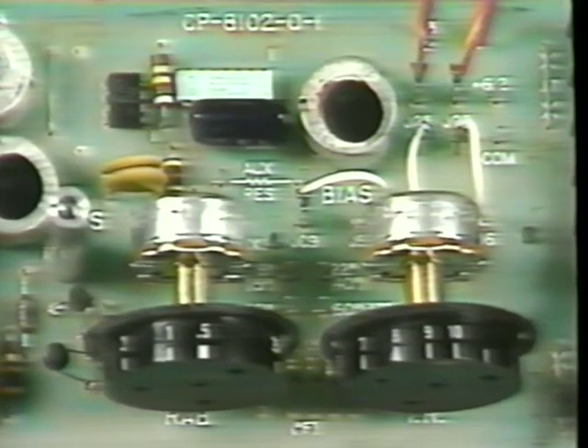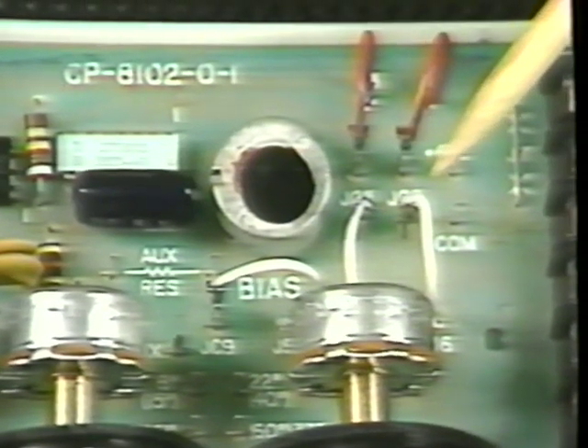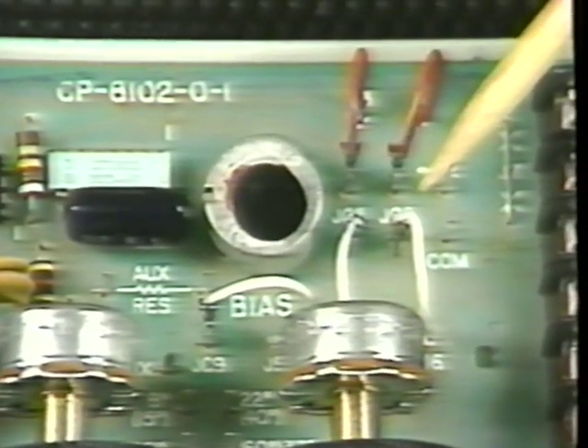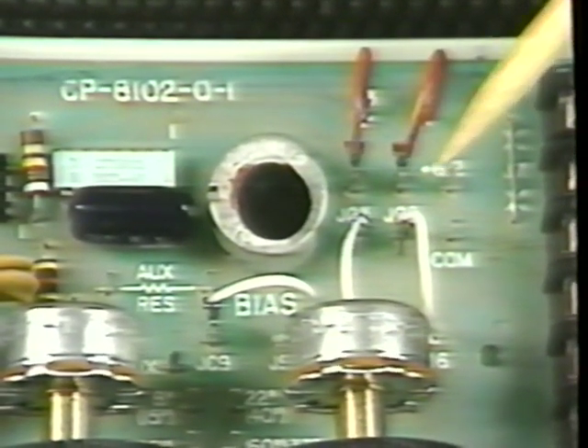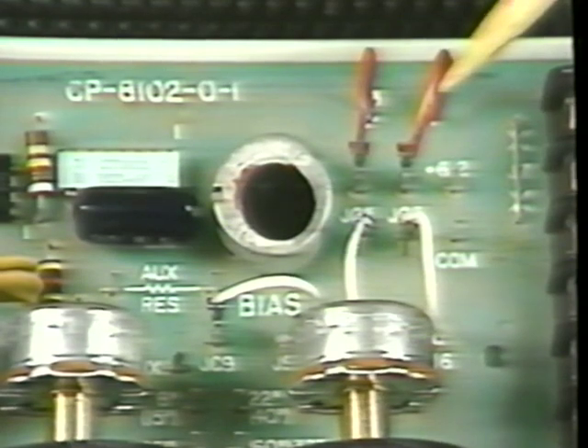The action jumpers. Two pair of jumpers in the upper right-hand corner of the controller determine both its action, direct or reverse action, and its reset, direct or reverse reset. The jumpers as shown here are in the factory position. That provides for direct action with reverse reset.